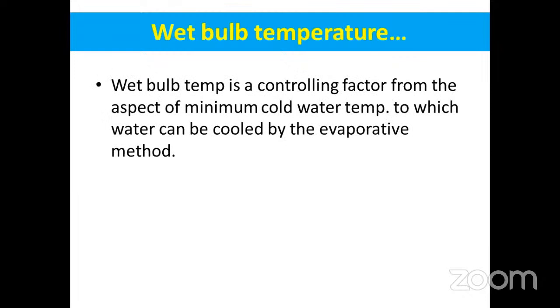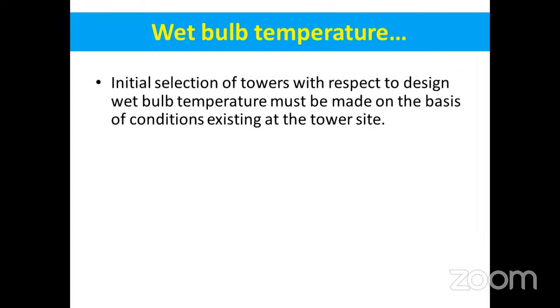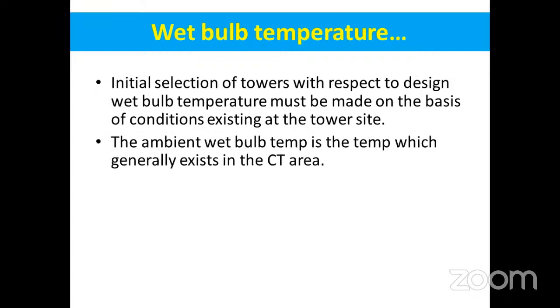Wet bulb temperature is a controlling factor from the aspect of minimum cold water temperature to which water can be cooled by evaporative method. This is the doubt someone has asked, sir. Initial selection of towers with respect to design: wet bulb temperature must be made on the basis of condition existing on the tower site. Tower site conditions also have to be considered for designing a tower, sir. Designing the system, entire system.